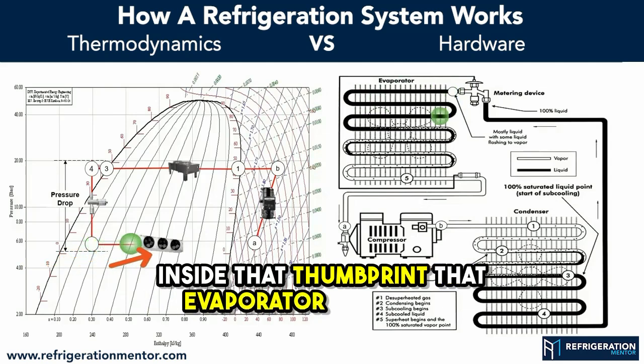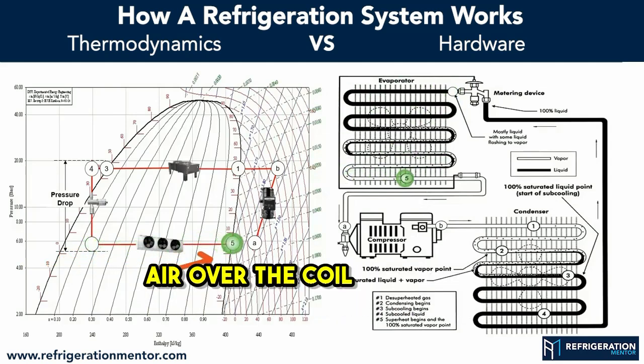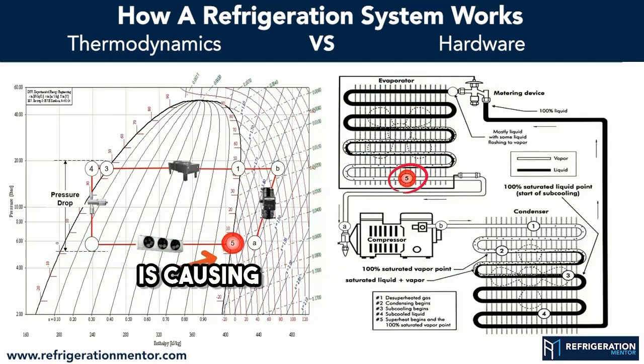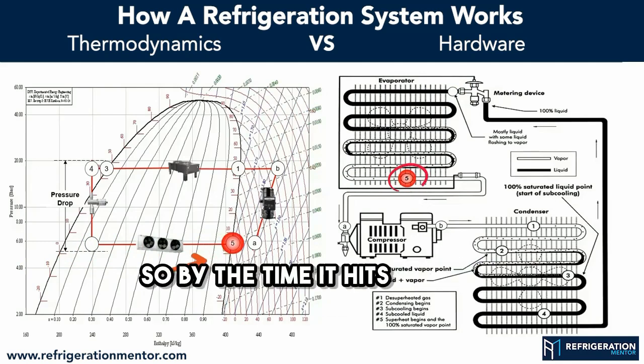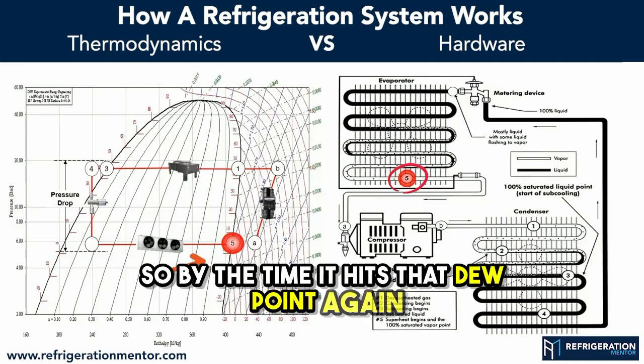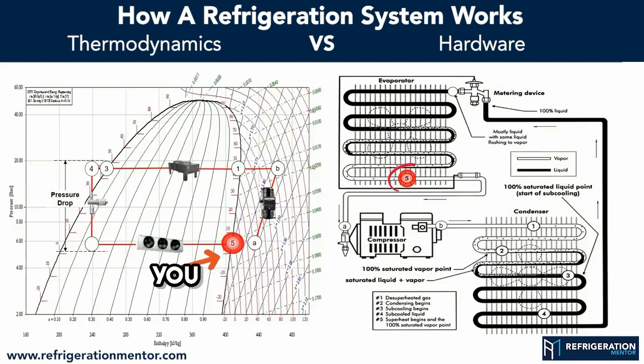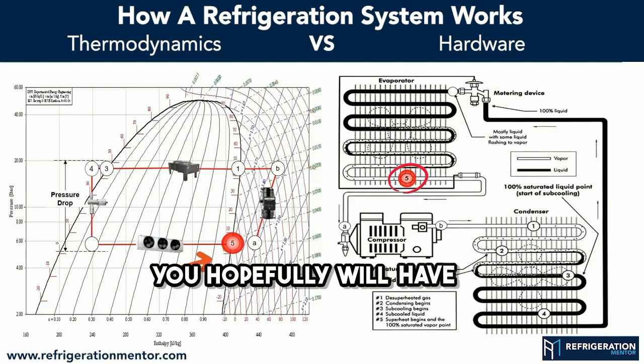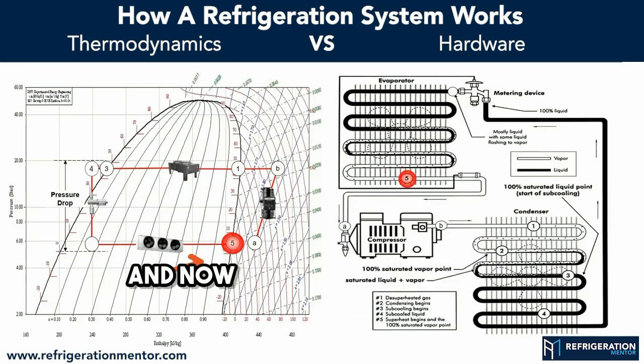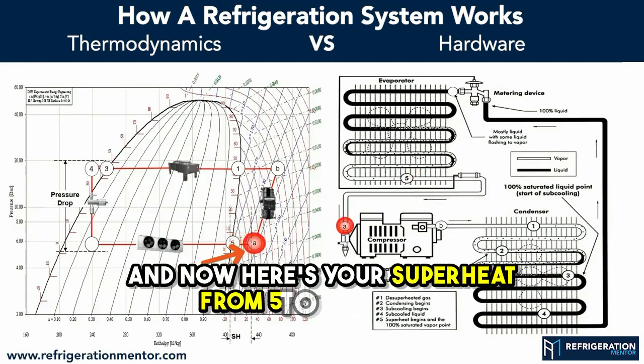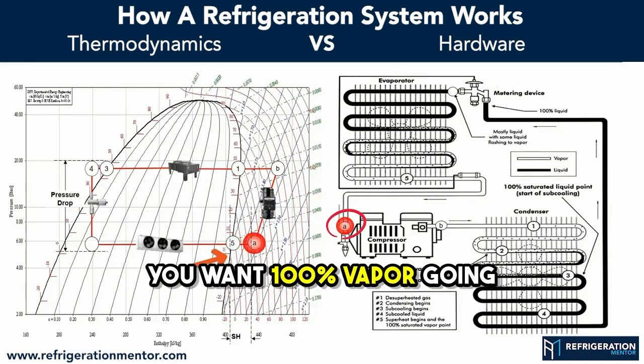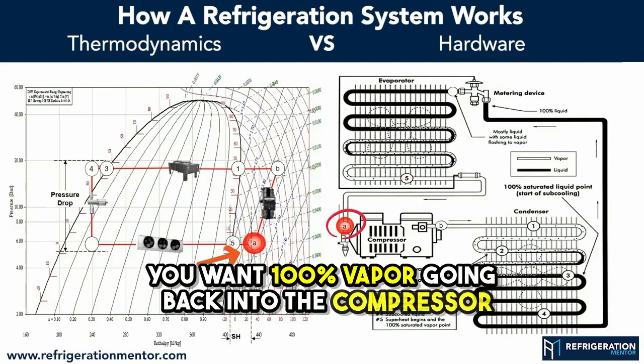That evaporator is blowing air over the coil, causing that refrigerant to boil. So by the time it hits that dew point again, you hopefully will have no liquid left. And now here's your superheat from 5 to A, because you want 100% vapor going back into the compressor.